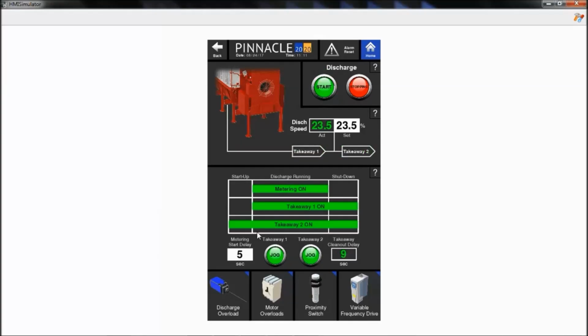Just because I'm on the screen and looking at it, I should also mention that there have been jog buttons introduced. These buttons bypass the regular starting and stopping sequence. These are meant to be used either for testing or if you have a discharge jam. These work as dead man switches, so while you hold the button down, that component will run. If I hold takeaway 1, that component turns on, and when I let go, it stops. So this is meant for testing a motor or trying to unjam your takeaway in the event that something gets plugged up.